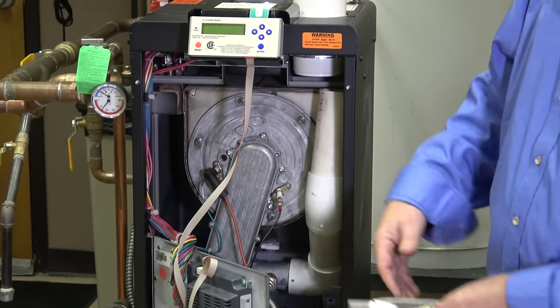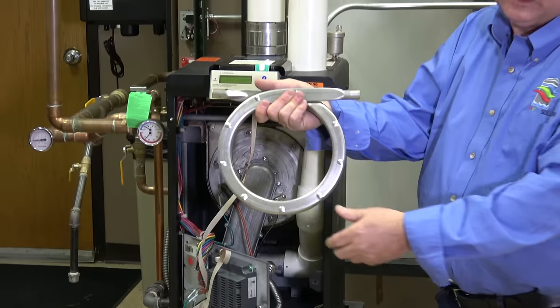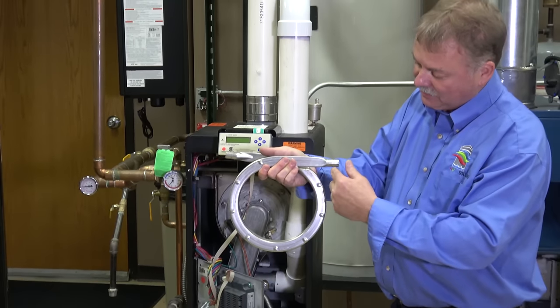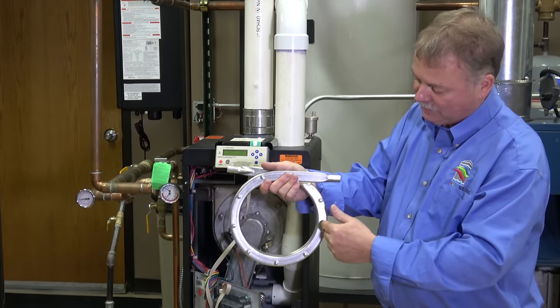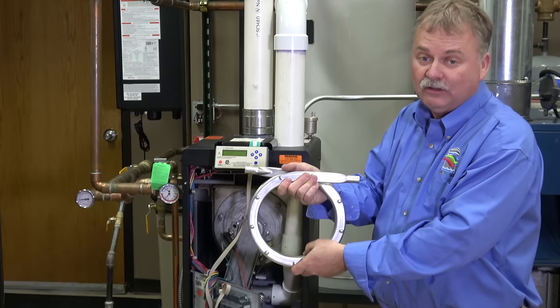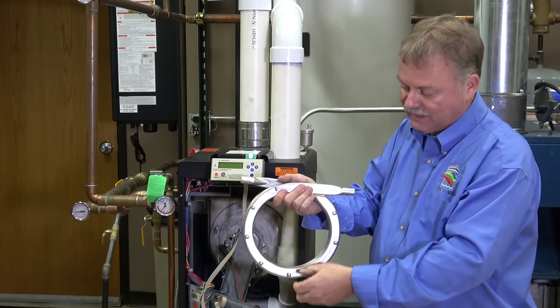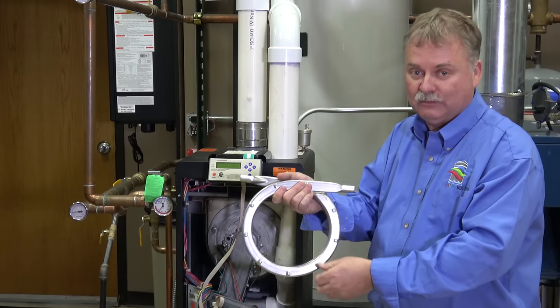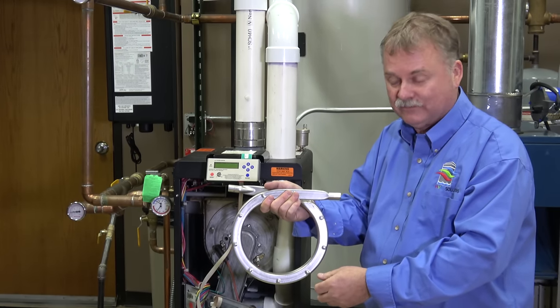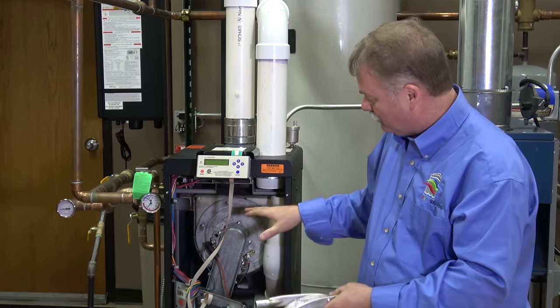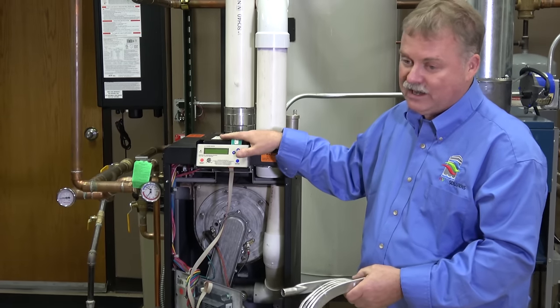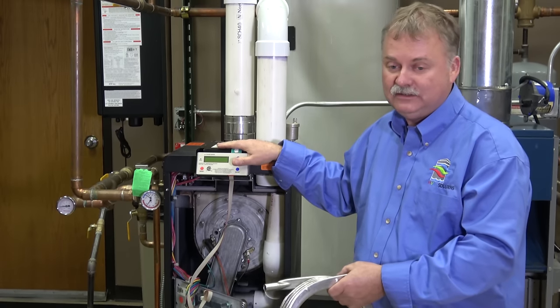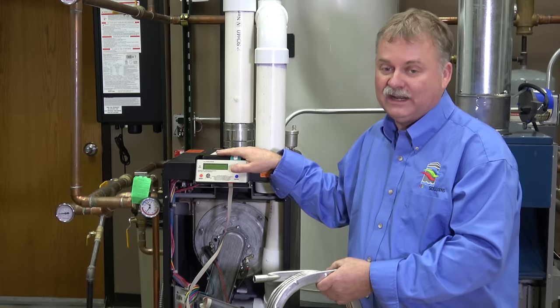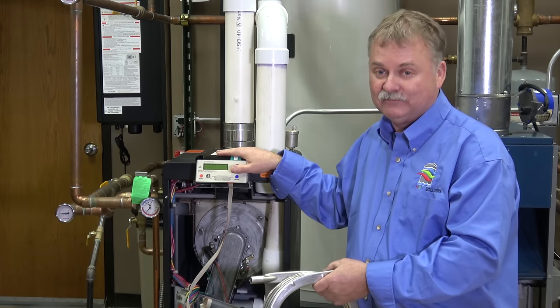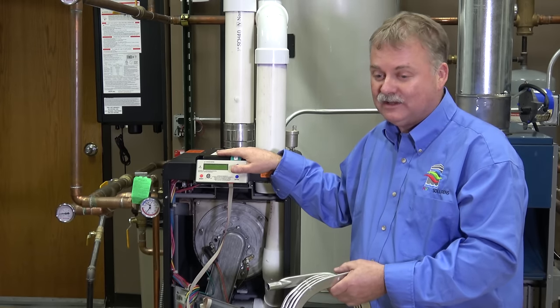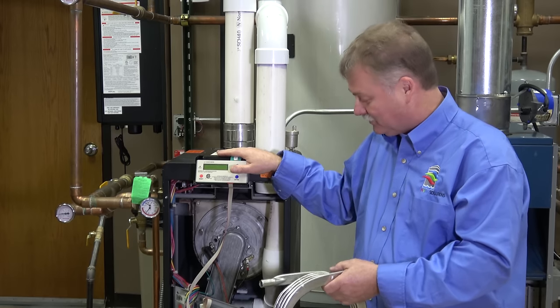If I open that door, what you would find is about seven or eight of these in there that actually has water inside this coil, actually transferring that flue gas into BTUs that we put into the hydronic heating system. Okay, so there's a bit more to these things, but now in this range, if you're in the condensing mode, you're looking at 90 to 95% efficient. Okay, so that saves a lot of money in the long run. So it's something to look at.